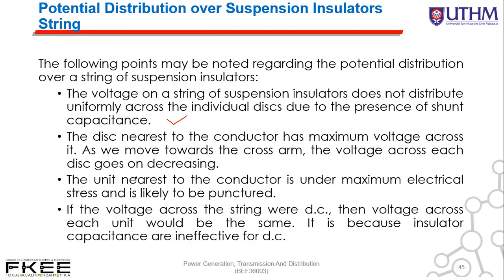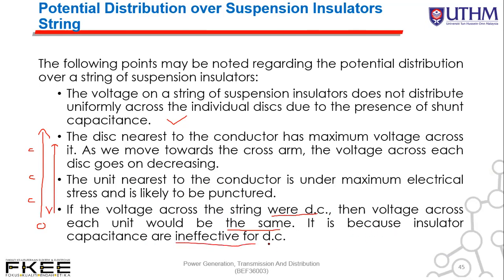As we move toward the cross arm (i.e., from bottom to top), the voltage decreases. The unit nearest to the conductor is under maximum electrical stress and is likely to be punctured first. If the voltage across the string were DC, the voltage across each unit would be the same, because capacitors do not function for DC.